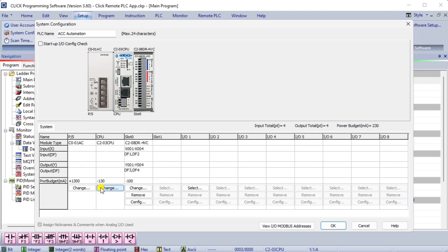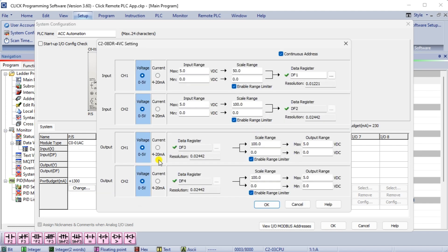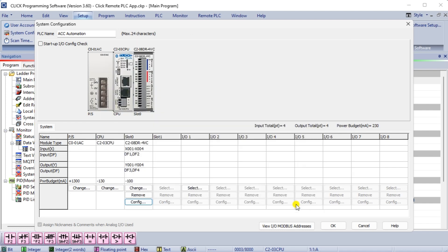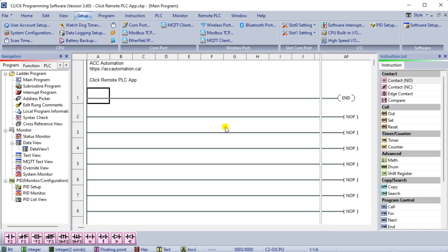If we look at the configuration of slot 0, we will see that the first analog input is set for 0 to 5 volts and the scale range is from 0.0 to 50.0 in DF1. Select cancel.